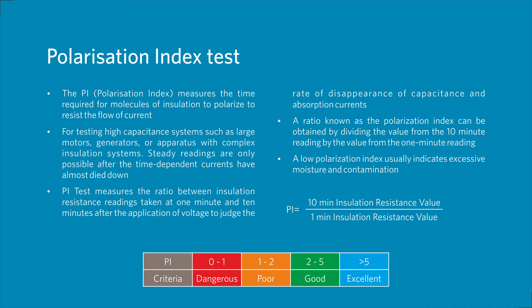Polarization Index is a ratio of the 10-minute insulation resistance value to the 1-minute insulation resistance value. It gives an inference of quality of insulation: if the value is between 0 to 1 it's dangerous; between 1 to 2 the insulation quality is poor; between 2 to 5 it's considered good; and greater than 5 is considered excellent. Please note the value is also assessed as per type and class of insulation.